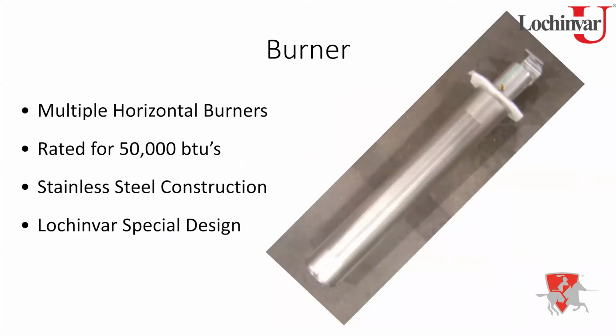First thing we'll talk about real quickly is the burner. These are rated at 50,000 BTUs each. So if you, for some reason, don't know the model number, maybe it's washed off on the rating plate, and that does happen, you need to know the size. If you know the number of burners you've got in the heater, you know what size you've got, right? Each one's 50,000 BTUs. So a 200,000 BTU heater has 4 burners in it, right? Yep. So I know what we've got. It's easy to deal with.